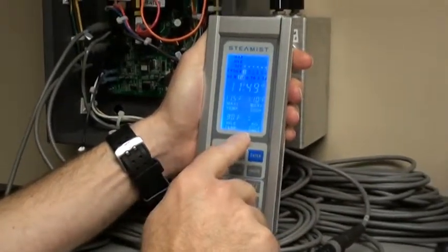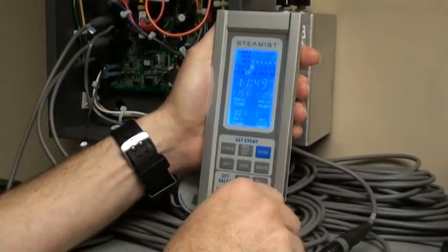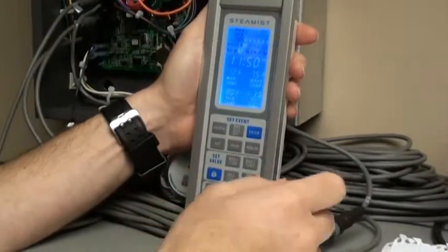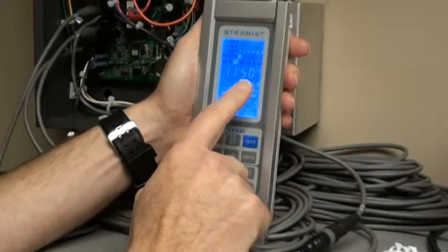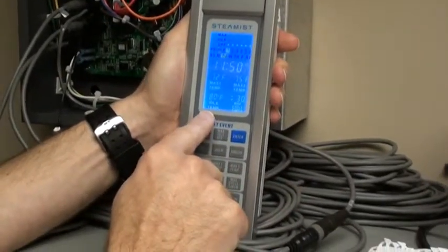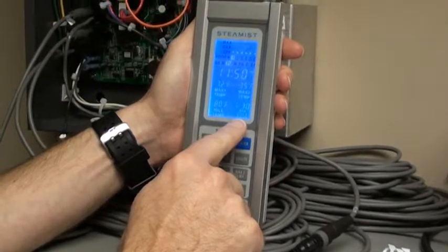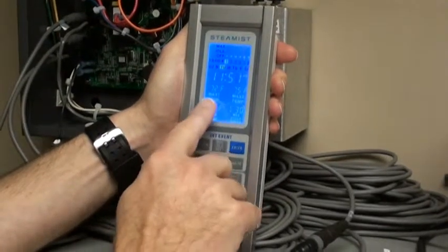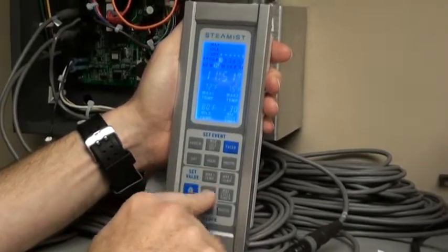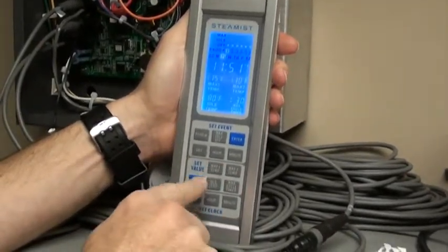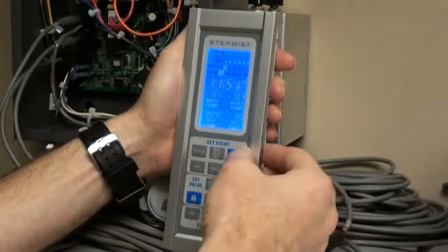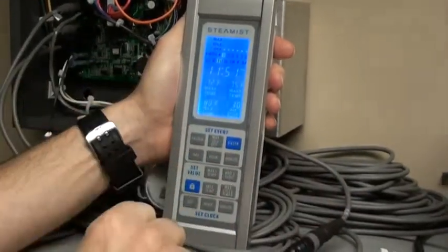Once you're done, if you don't want to wait for the flashing to go away, you can simply press the enter button. That'll lock it up. So right now, just to recap, it's 11:50 a.m. Our idle temp is 80, our max cycle timer is 30. Room 1 is 72 degrees as the ambient now, room 2 is 75. To check the set points, we just press max 1, our set point is 115, max 2 is 110. Again, I press enter, that'll lock it up.